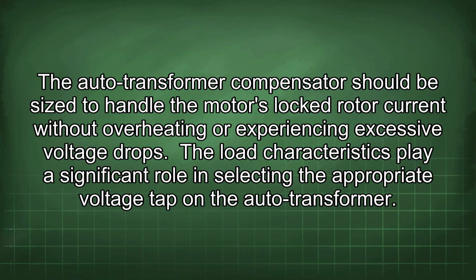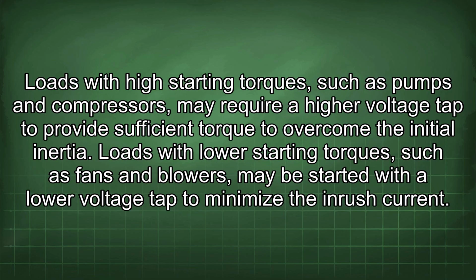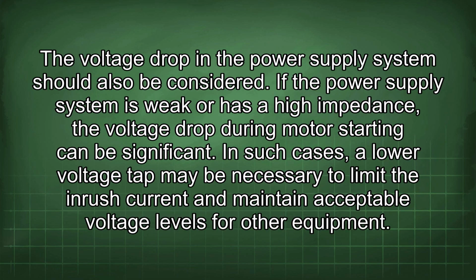The load characteristics play a significant role in selecting the appropriate voltage tap on the auto transformer. Loads with high starting torques, such as pumps and compressors, may require a higher voltage tap to provide sufficient torque to overcome the initial inertia. Loads with lower starting torques, such as fans and blowers, may be started with a lower voltage tap to minimize the inrush current. The voltage drop in the power supply system should also be considered.